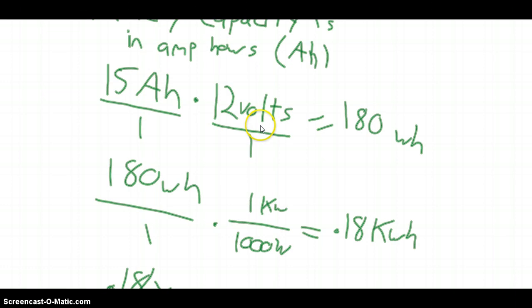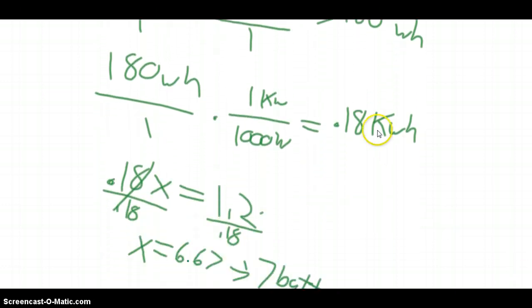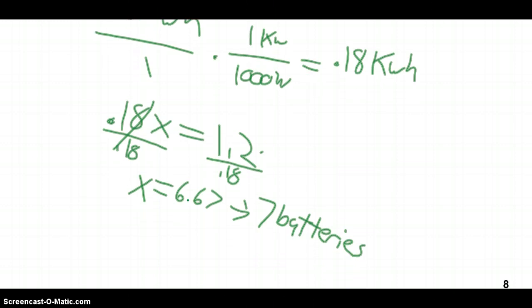We multiply that by 12 volts because amps times volts equals watts. So we get amps times volts equals watts, and then we still have the hour. So we get 15 amp hours is 180 watt hours. Then we convert to kilowatt hours. So this battery stores 0.18 kilowatt hours. And since we want to store 1.2 kilowatt hours, again, it's weird that it turned out like this. It's not always going to be the case by a long shot. But we need to have seven batteries.